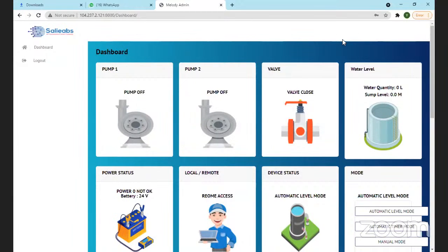Now you can see the power status is not okay, which means there is no power supply from this pumping station, and the IoT gateway is working on 24 volts. That is why both pumps are off—there is no power supply, there is a power shutdown in the pumping station.